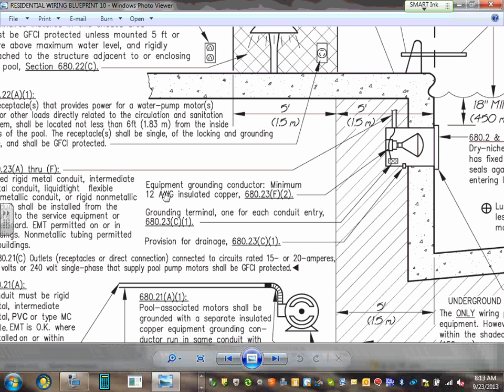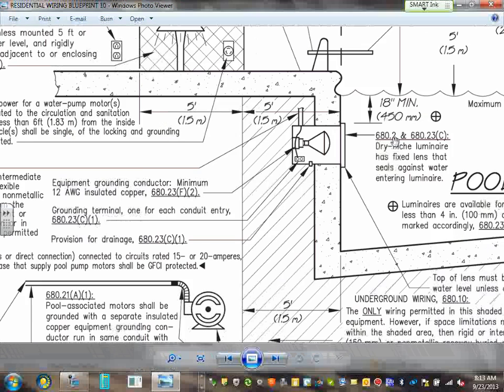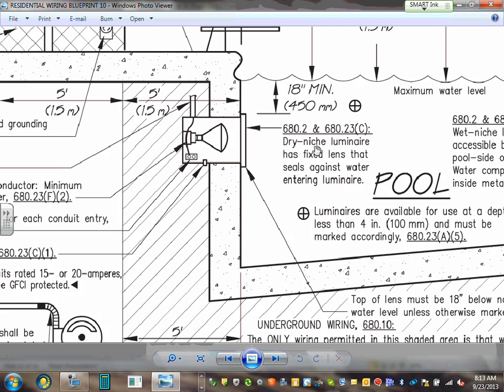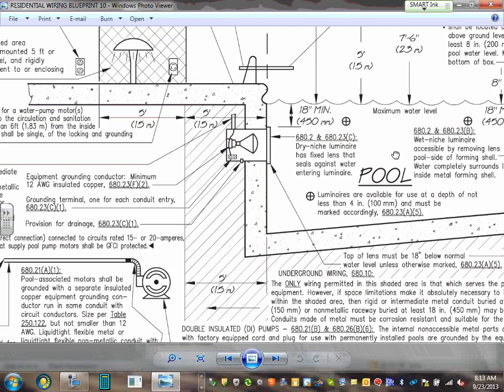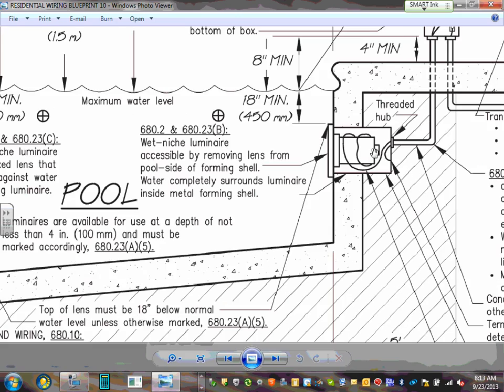You need an equipment grounding conductor, number 12 at least, that comes to the fixture. Grounding terminal, one for each conduit entry. So as you put in the entry, you ground the conduit as well. This is what we call a dry niche luminaire. It has a fixed lens, so it's dry over here. Dry, the water cannot get in, to seal the water. I think there's a wet niche luminaire. Here you go. Here's a wet niche luminaire.